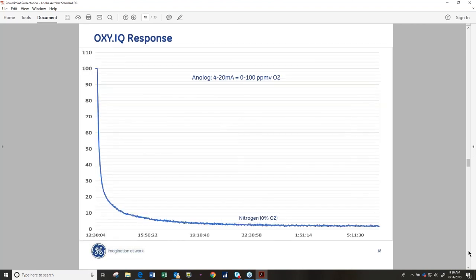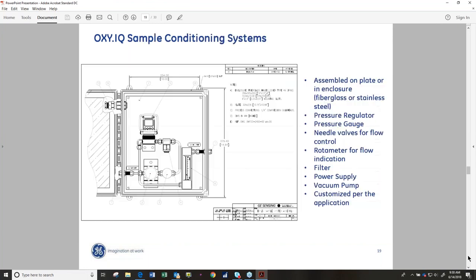And this is 100 ppm to virtually zero again. So in this case, you can see that from 100 ppm to about 5 or 6 ppm actually took a couple of hours. The initial change is quick, but to get those last remaining molecules of oxygen registered or out of there, it takes considerable time. Now it will go upward in the other direction quite fast. Next slide, please.